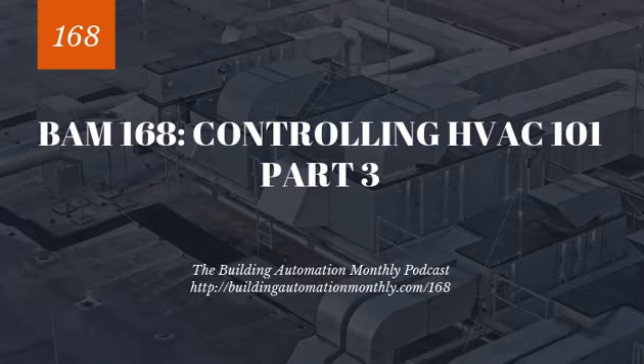That way they can run independently, because if you were trying to run them off pumps and valves and towers that were sized to a primary chiller that was maybe 1,000 tons, and this is a small little 200-ton chiller, you could overload the system. That's why they typically have their own pumps. So folks are often wondering, why do the little partial load chillers have their own pumps, their own towers, etc.? It's because of this exact reason.